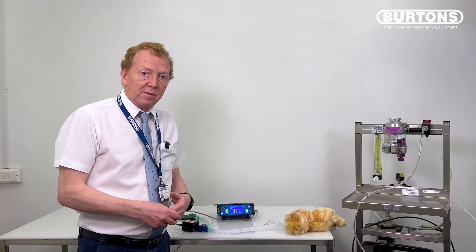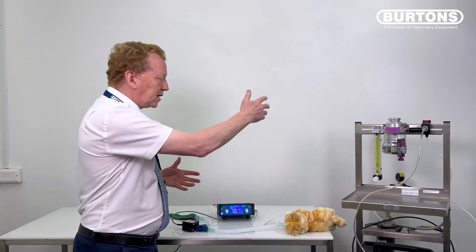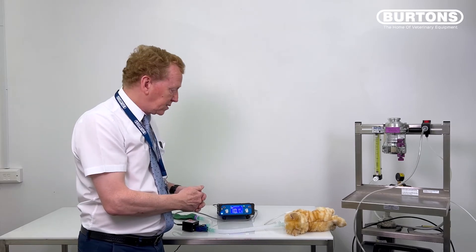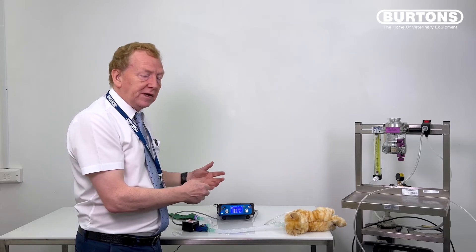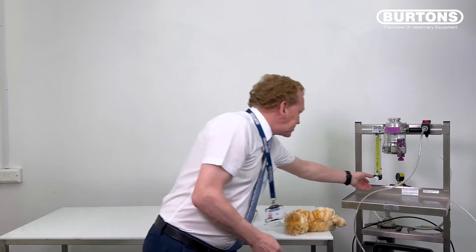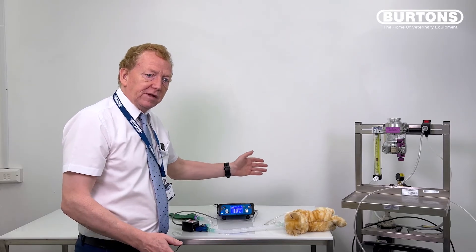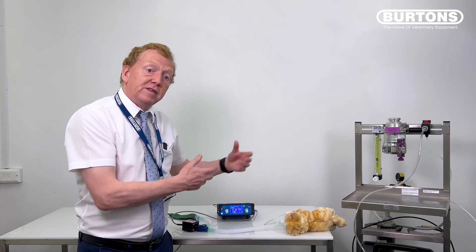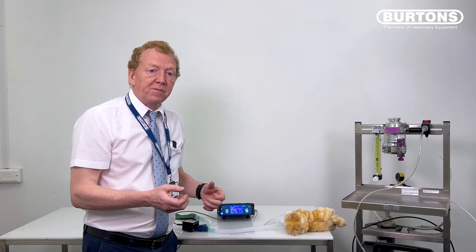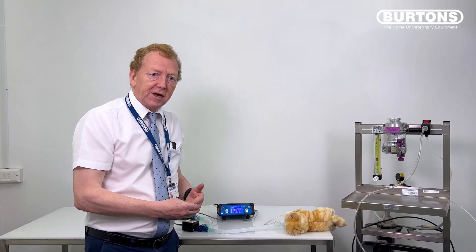So in a nutshell: SAVO4 morning check — look for the runtime, do your thumb leak test, do the dynamic test if you have any concerns, connect up in this manner, and calculate your fresh gas flow. Begin ventilating if needed; if not, the patient breathes it as a T-piece. When ventilating, adjust fresh gas flow to change inspiratory time, adjust expiratory time to change respiratory rate, and ventilation pressure dictates tidal volume — increase peak inspiratory pressure if chest inflation is insufficient, decrease if excessive. For more detail on this device, see the SAVO4 general videos. Thanks for watching.